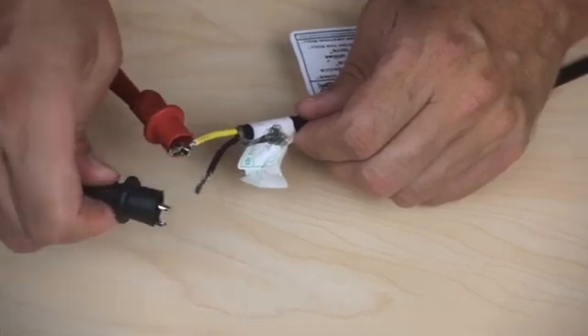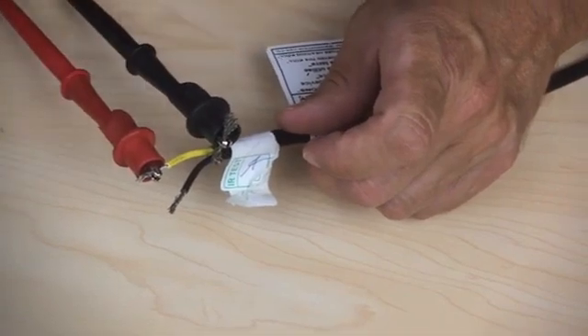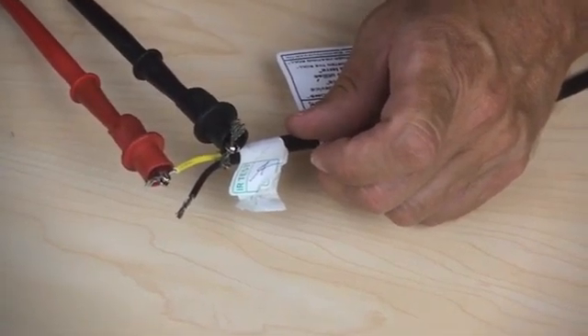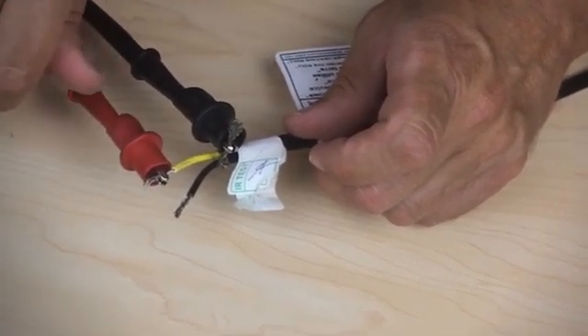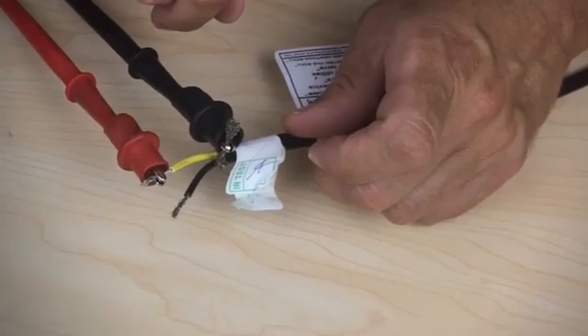We should not be getting ohms from the yellow or red wire to ground. You want to see if your ohmmeter is giving you any ohms readings. It should be displaying OL or a 1 or INF.